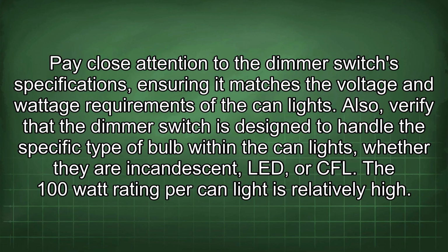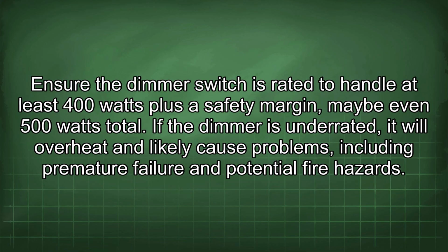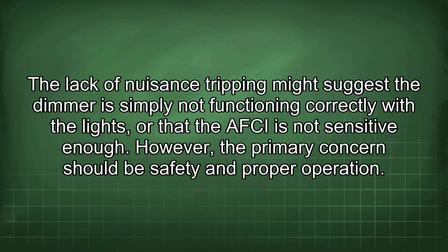The 100 watt rating per can light is relatively high. Ensure the dimmer switch is rated to handle at least 400 watts plus a safety margin, maybe even 500 watts total. If the dimmer is underrated, it will overheat and likely cause problems, including premature failure and potential fire hazards. The lack of nuisance tripping might suggest the dimmer is simply not functioning correctly with the lights, or that the AFCI is not sensitive enough. However, the primary concern should be safety and proper operation.